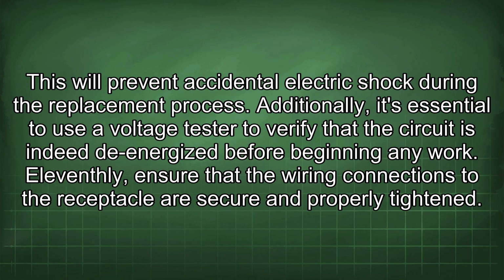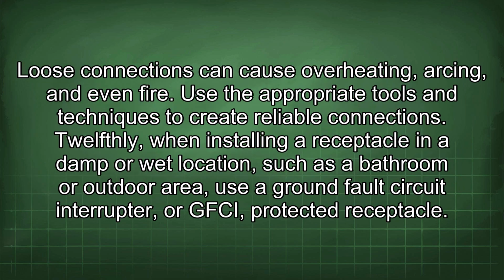Additionally, it's essential to use a voltage tester to verify that the circuit is indeed de-energized before beginning any work. 11thly, ensure that the wiring connections to the receptacle are secure and properly tightened. Loose connections can cause overheating, arcing, and even fire. Use the appropriate tools and techniques to create reliable connections.